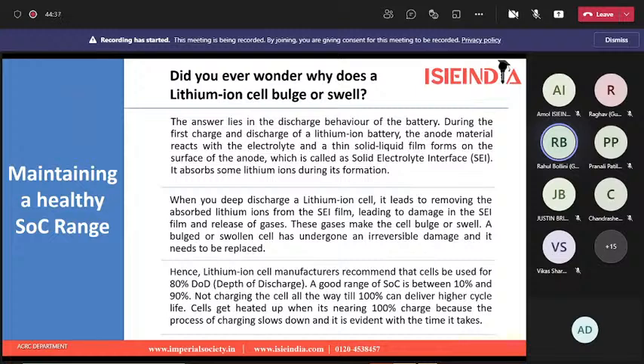A healthy SOC range, according to most manufacturers' datasheets, means not discharging the battery more than 80% - so depth of discharge should be 80%. I believe maintaining a 10% lower cutoff and 90% upper cutoff lets you discharge the battery healthily within that 80% range, avoiding deep discharge issues and excessive time spent charging above 90%.